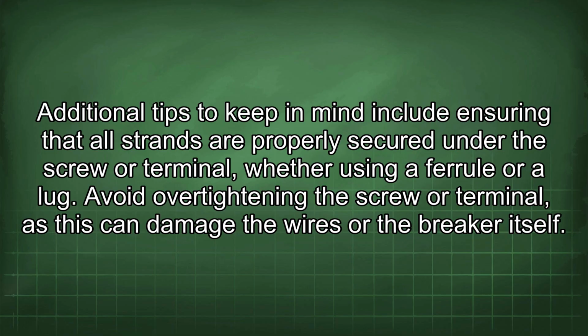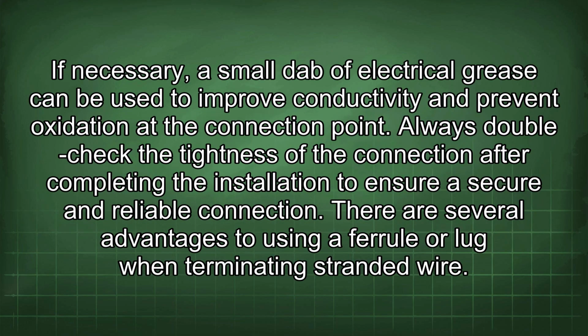Additional tips to keep in mind include ensuring that all strands are properly secured under the screw or terminal, whether using a ferrule or a lug. Avoid over-tightening the screw or terminal, as this can damage the wires or the breaker itself. If necessary, a small dab of electrical grease can be used to improve conductivity and prevent oxidation at the connection point. Always double-check the tightness of the connection after completing the installation to ensure a secure and reliable connection.